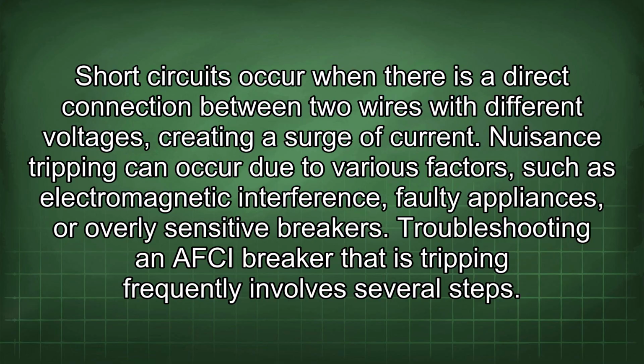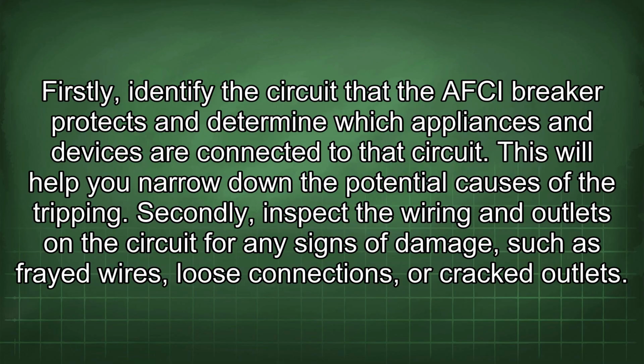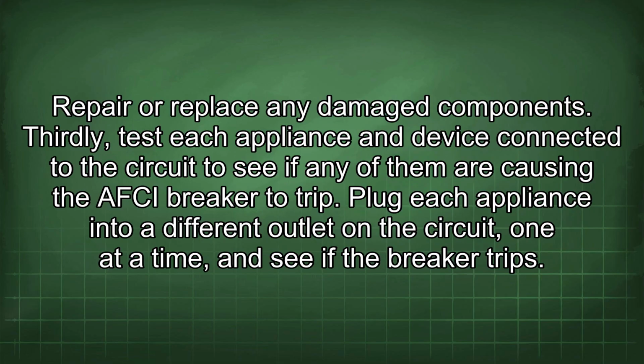Troubleshooting an AFCI breaker that is tripping frequently involves several steps. Firstly, identify the circuit that the AFCI breaker protects and determine which appliances and devices are connected to that circuit. This will help you narrow down the potential causes of the tripping. Secondly, inspect the wiring and outlets on the circuit for any signs of damage, such as frayed wires, loose connections, or cracked outlets. Repair or replace any damaged components. Thirdly, test each appliance and device connected to the circuit to see if any of them are causing the AFCI breaker to trip.